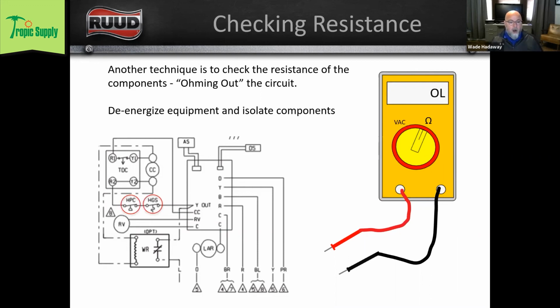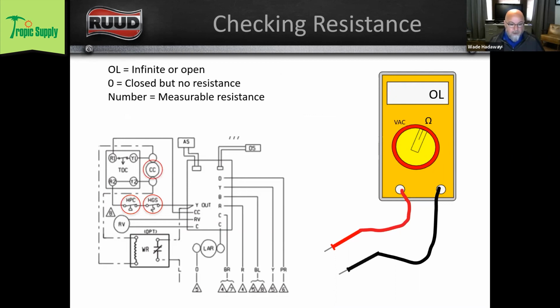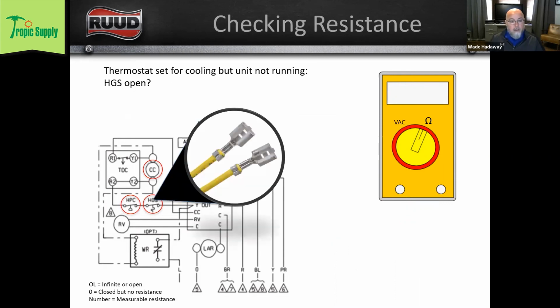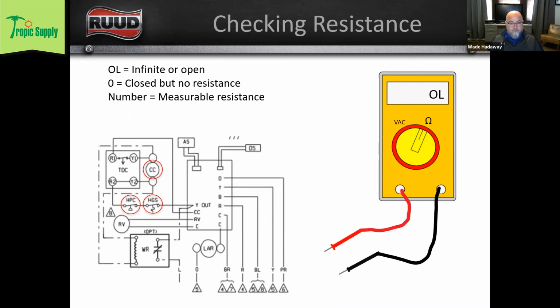Again, we're going to check our hot gas, our high pressure, and our contactor coil. Those are our 3 loads. So first thing you got to do is disconnect the terminals. Let me go back one slide. So there's 3 things that our meter is going to read when we're checking resistance or ohming out a component. It's going to read OL, which is infinite or open.